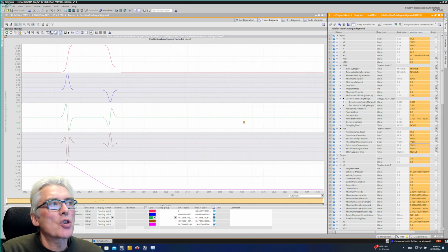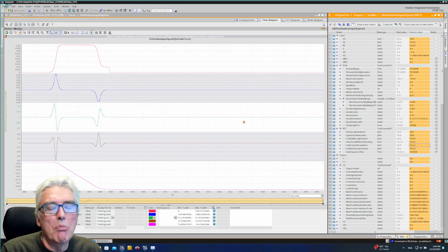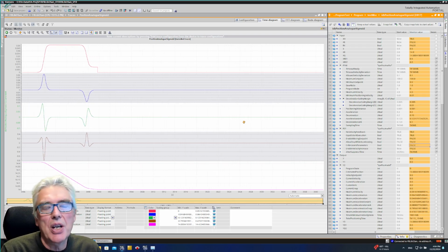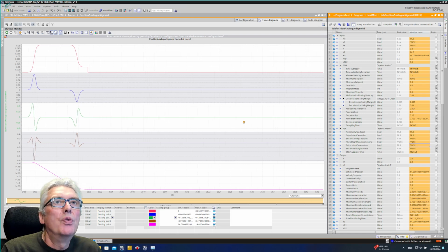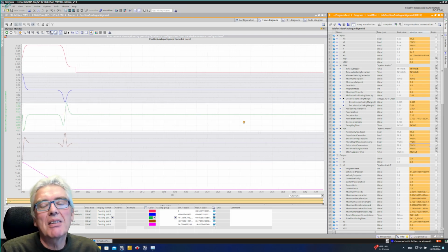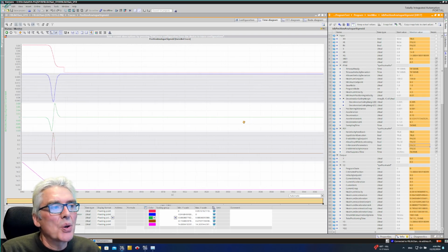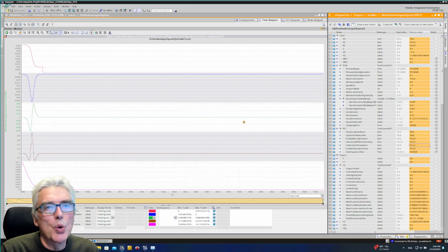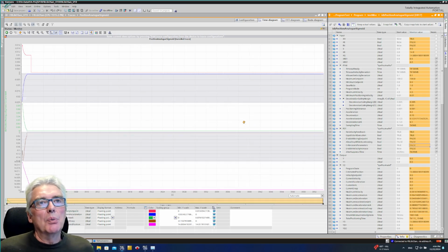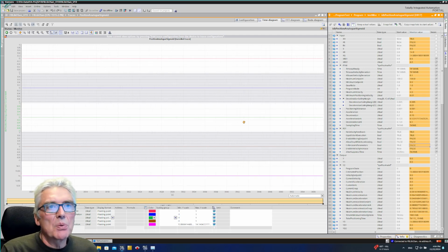You could just embed it and then implement the PLC open speed profiles, maybe in a single function block. Usually they call it instructions, but we are looking at objects here, and a speed drive is an object that we are trying to move in a nice speed profile. So it would be a multifunctional function block, where this will be the workhorse doing the positioning, and the wrapper. If you do jogging, we set program mode, jogging positive direction, program mode 2 or 3, 2 in positive, and a low speed set point, and then we do the jogging, switch off the jogging, jog in the opposite direction, and so on.